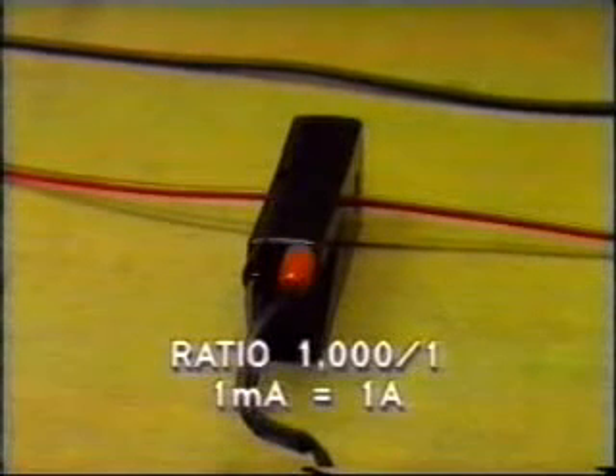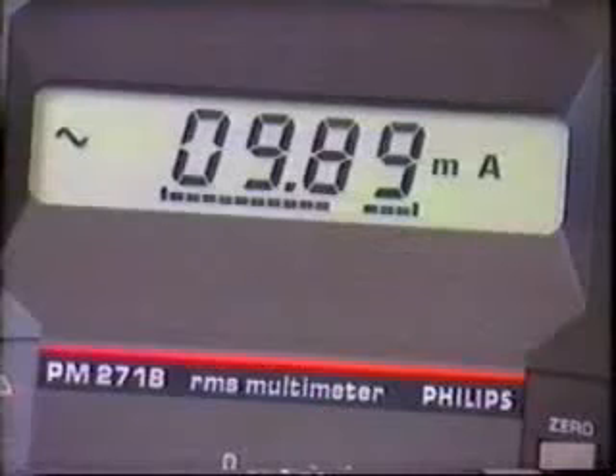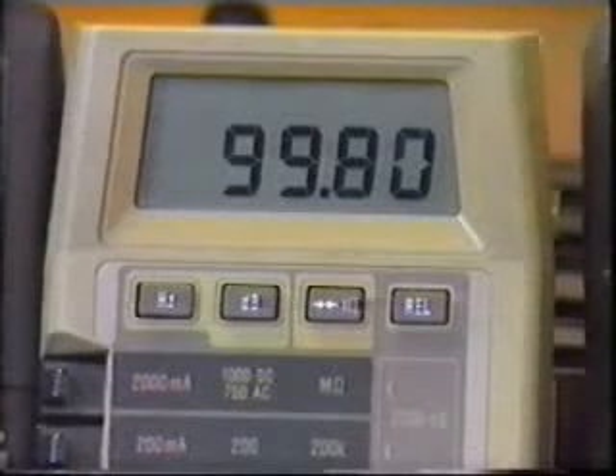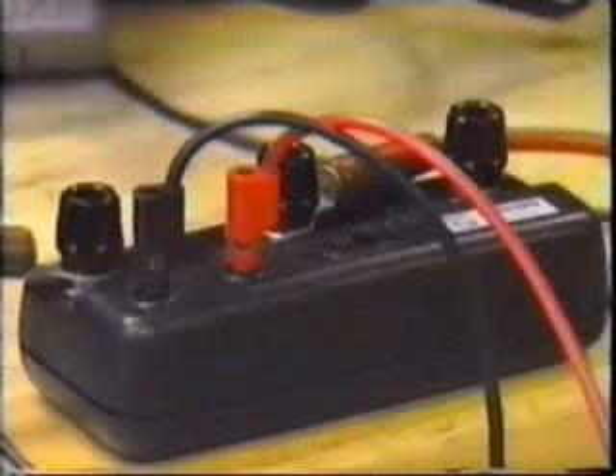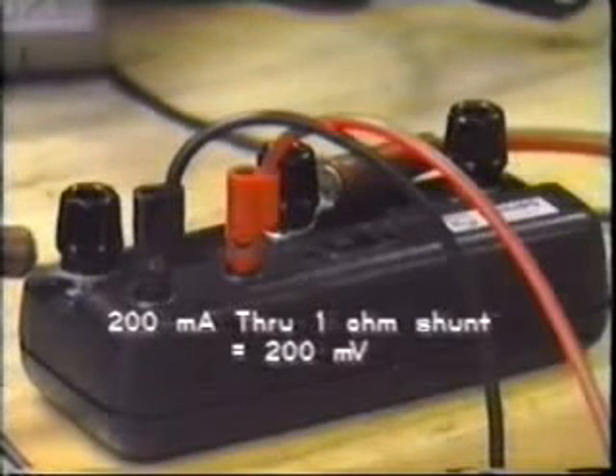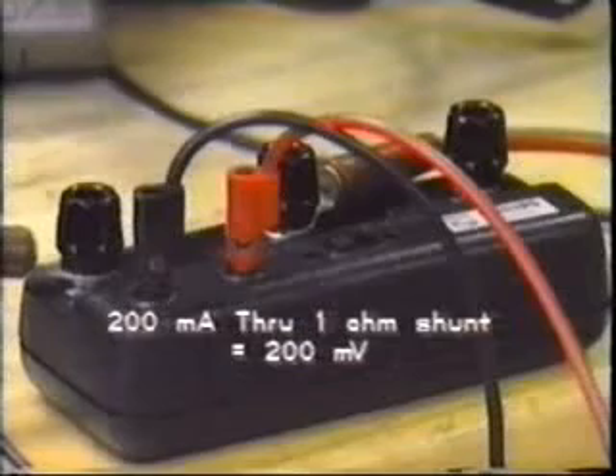One type of probe consists of a CT, usually wound with a convenient ratio of 1,000 to 1, so that 1 milliamp responds to 1 amp on the circuit being measured. The output can be measured by a multimeter or a millivolt meter with a suitable shunt. For example, 200 milliamps through a 1 ohm shunt would give us a reading of 200 millivolts.